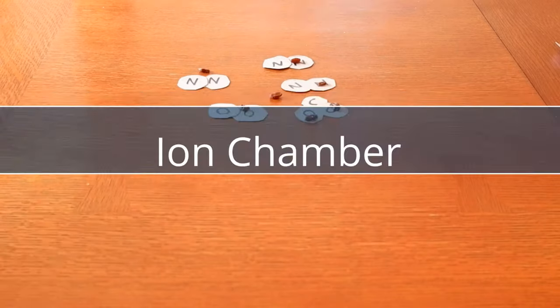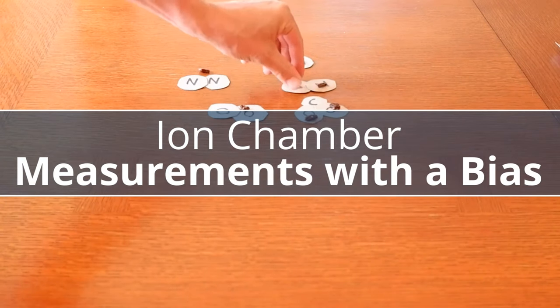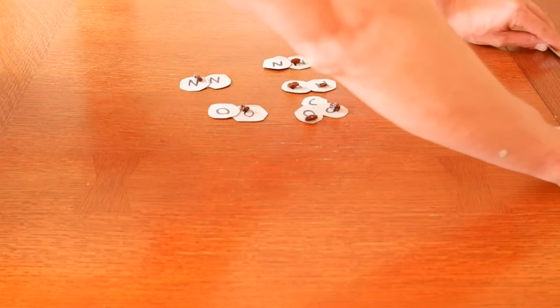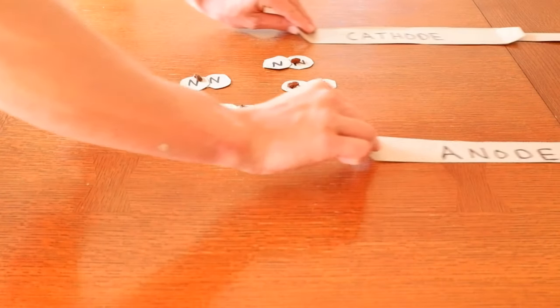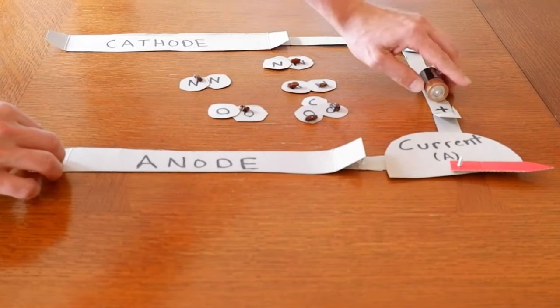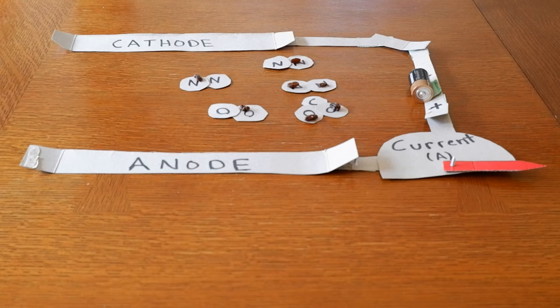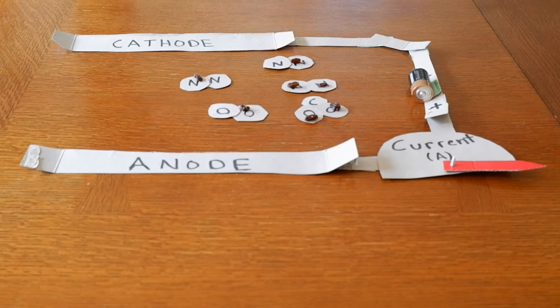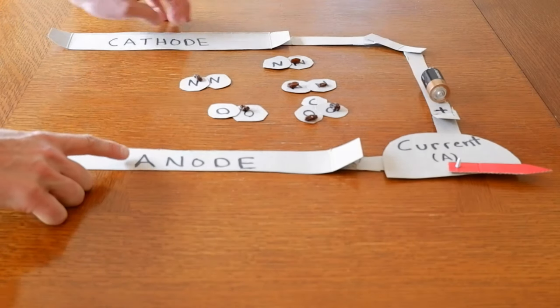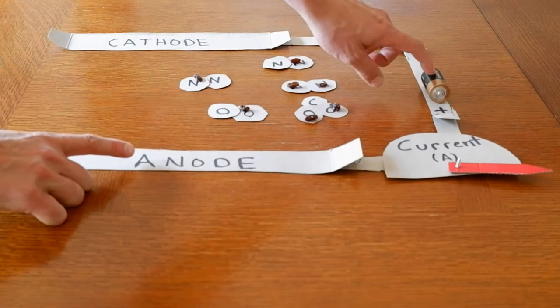The idea of what's called an ion chamber is to try and measure that effect. So we'll bring in our ion chamber, and you can have different geometries of these ion chambers. I'm just showing you one geometry. We call this a parallel plate geometry of an ion chamber because we have these two metal plates, and then between those two metal plates, we have a potential.